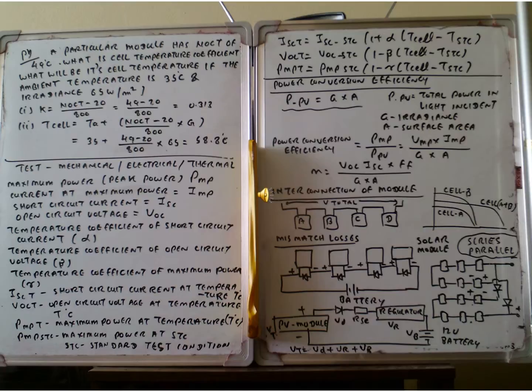The important one is that solar cells are producing electricity. If one cell is accidentally shaded, the cell will no longer produce electric current. And instead, it will absorb all energy produced by the other cells so that this cell will be overheated and overloaded and can be damaged. Therefore, we have to connect bypass diodes. We are connecting bypass diodes. So if one cell is accidentally shaded, the other cells instead will bypass the cell by passing through the bypass diodes. This is the important one. This is what we also call the mismatch process.